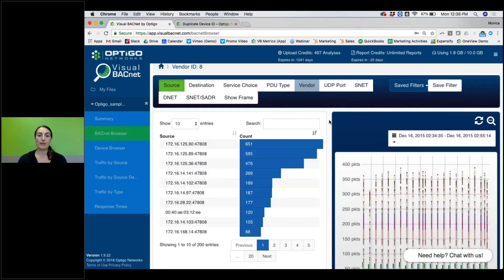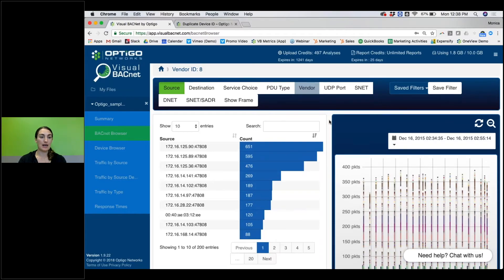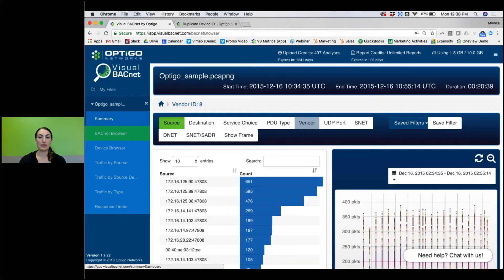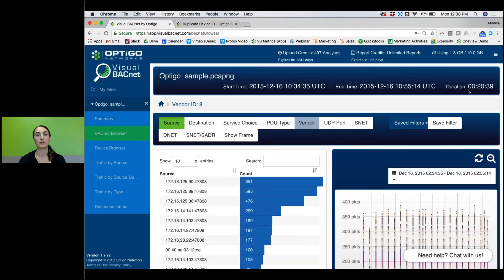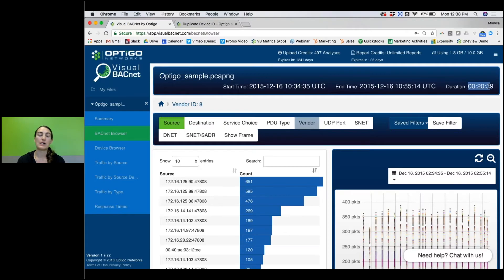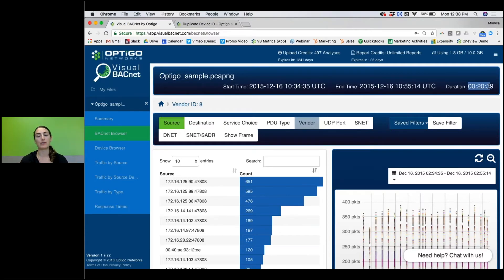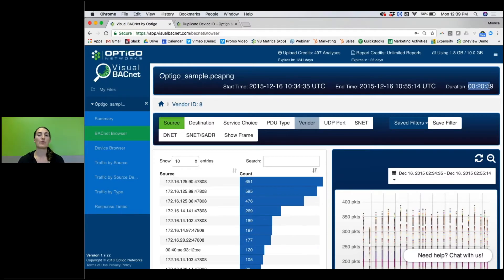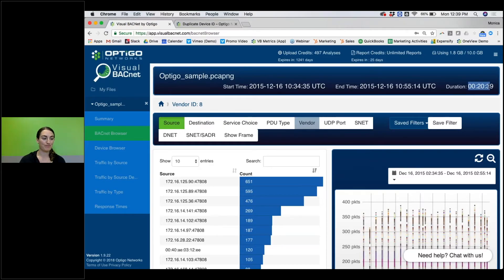A couple of best practices. We recommend doing an hour-long capture if you're doing a general health check on a site. This one's about 20 minutes. You can see the duration up here. Longer, up to an hour is good. It can usually capture all of those things that happen on a regular basis. Of course, if you have a problem that happens at a specific time, capture at that specific time.